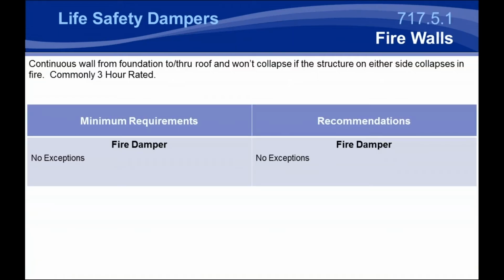Getting into the bulk of the presentation, we will get into the most restrictive barriers, and we'll go to the least restrictive when we get towards the end of the presentation. Now, firewalls are typically one of the most restrictive, and commonly they're 3-hour rated. It's a continuous wall from foundation through the roof, and it makes sure it won't collapse if the structure on either side of this barrier collapses.